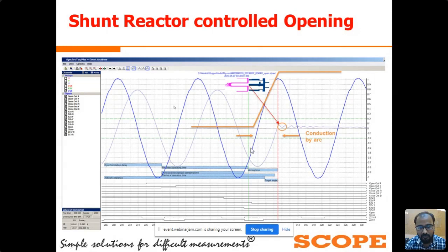After this point, from this point to this point, the current continues to flow between the CB contacts. But after reaching the end, the system current goes naturally to zero. At this moment, the dielectric strength between the CB contacts is more than the system voltage. We can see the waveform in dark, this is the voltage waveform, and this line in orange is the dielectric strength. At this point, the dielectric strength between the CB contacts is more than the system voltage. So due to that, there is no reignition once the current goes naturally to zero.